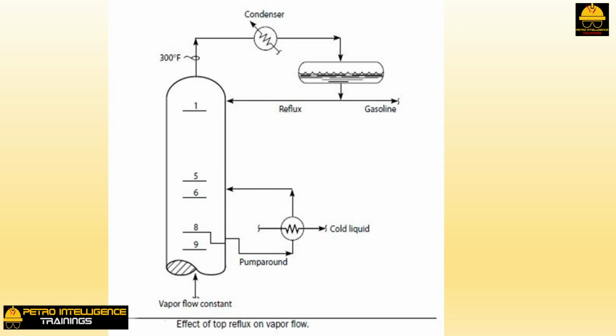How top reflux affects vapor flow. Let's assume that the vapor flow into a tower is constant. Picture shows such a situation. Both the pounds per hour and temperature of the vapor flowing up to tray 9 are constant. This means that the heat flow into the tower is constant. Now, let's increase the reflux rate. Certainly, the result will be the tower top temperature will decrease. The gasoline overhead product flow will also decrease.